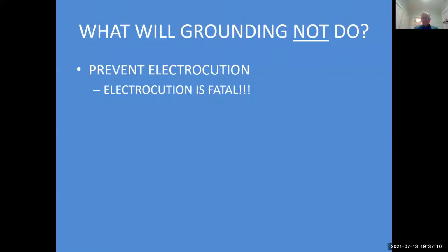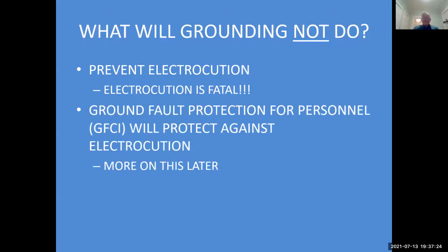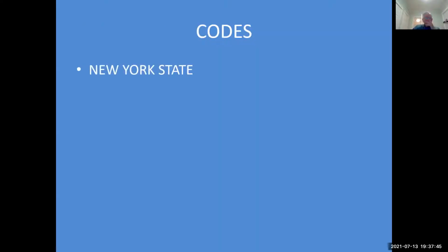What won't grounding do? It won't prevent electrocution, and electrocution is fatal. Many times it's misused in the news, so they say someone was electrocuted and is recovering. If you're electrocuted, you're toast. Ground fault protection will protect against electrocution. And the ground fault circuit interrupters that you typically have in your house do not require a connection to ground to function. It's purely a differential device that's looking at the output and the input, and when they're not the same, it trips.